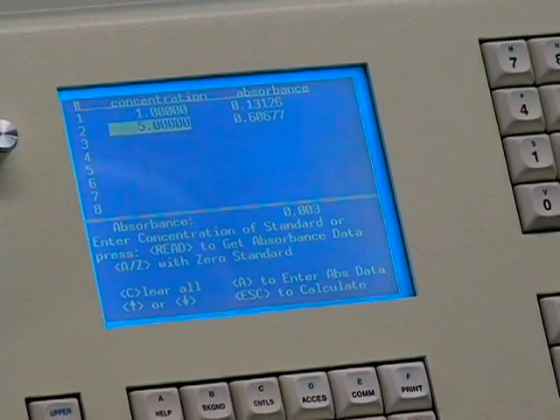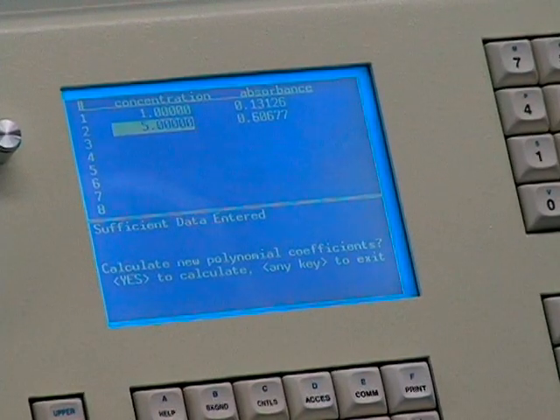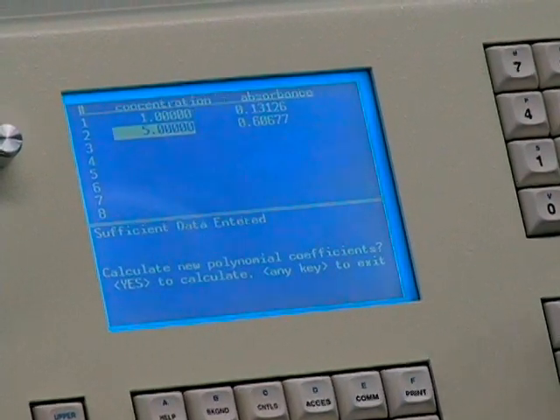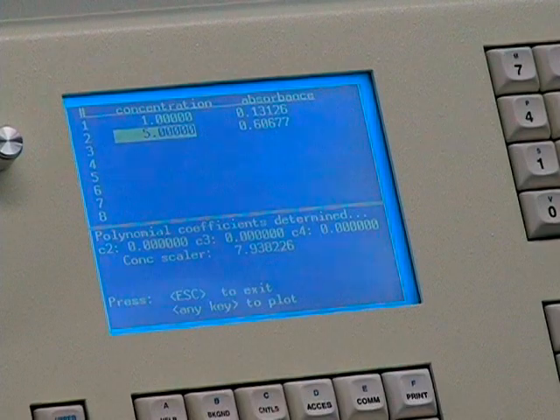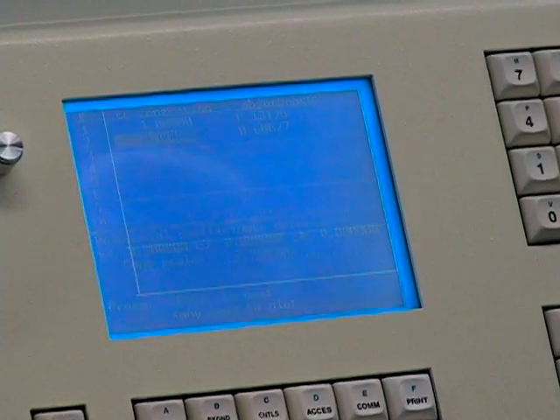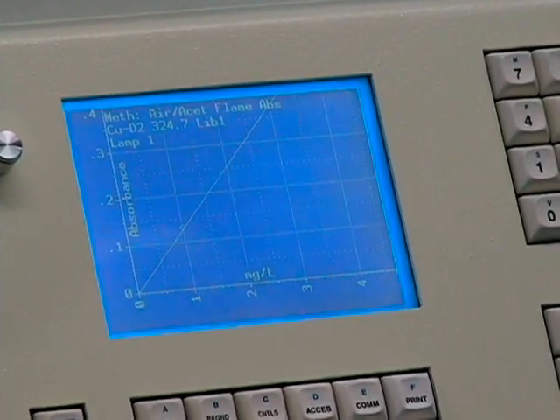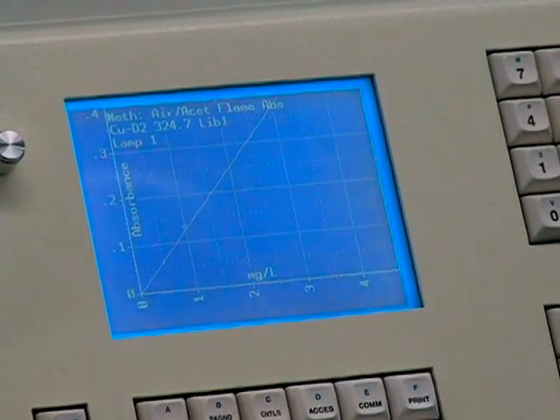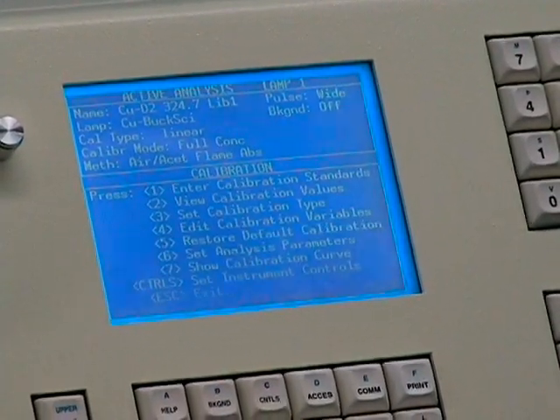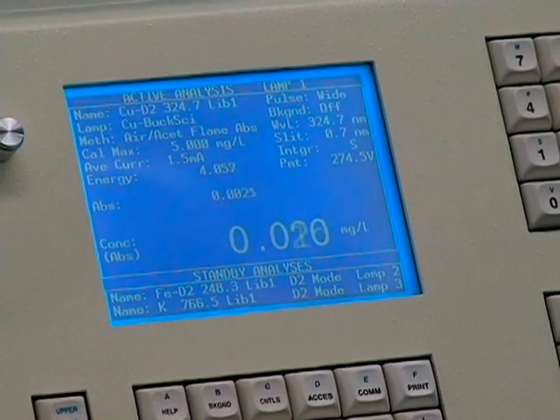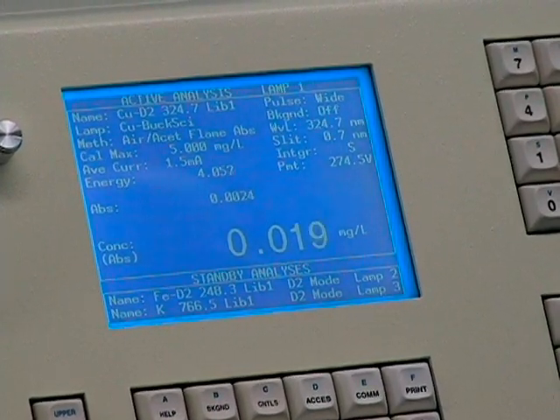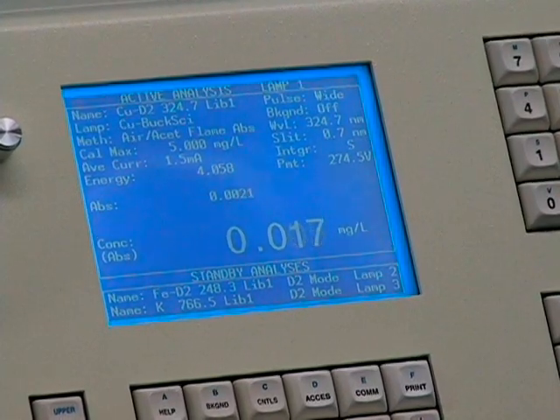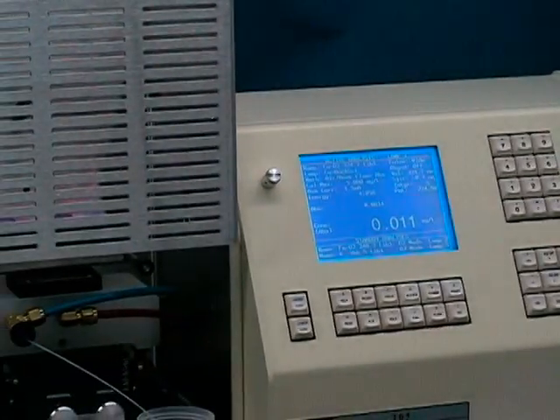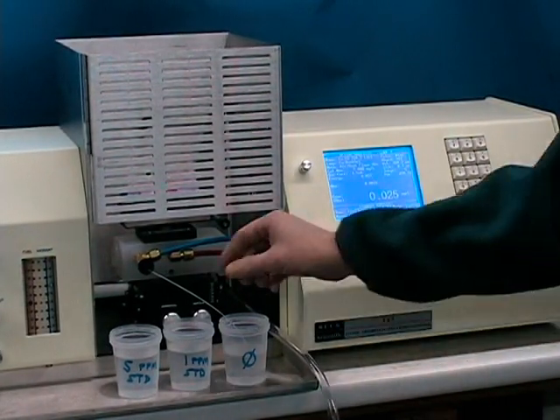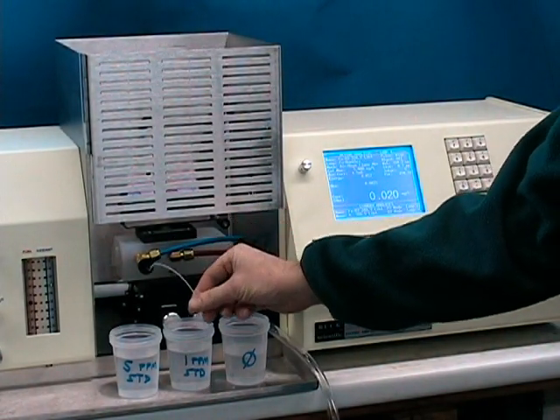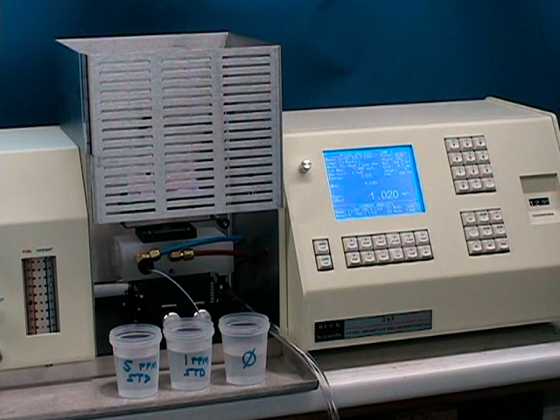Press the escape key. You'll see your options there. Press yes to calculate the concentration curve, and then press the enter key to actually see the graphical curve. If this looks satisfactory, you may press the escape key 3 times to return to the active analysis screen, and you can see we are now in the ppm mode for concentration analysis. At this point, we can check a standard or a sample and get our readings.